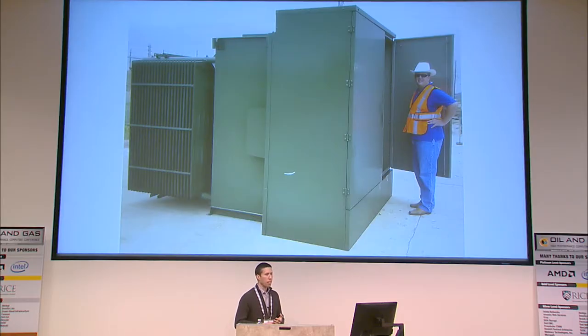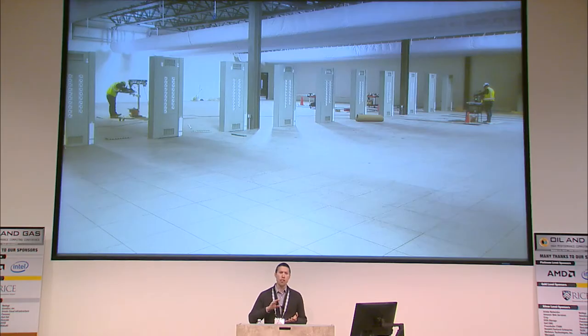This was very non-standard—none of the electricians wanted to deal with it here. We had to work closely with Skybox and the utility to make this happen, and we were able to. This flows all the way through the design, creating new efficiencies as we go. Because it's 240 volt, we're running at lower current, which means we can get away with fewer circuit boards, fewer circuit breakers, fewer PDUs, fewer of everything.